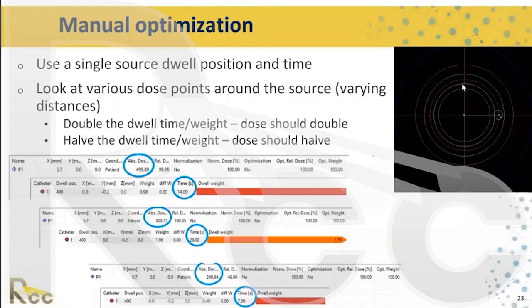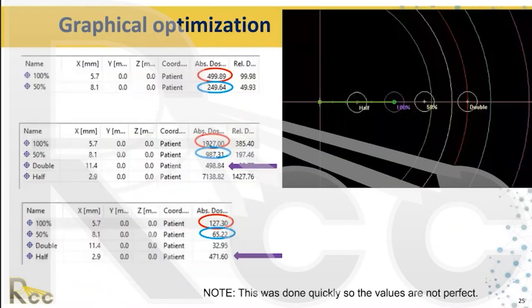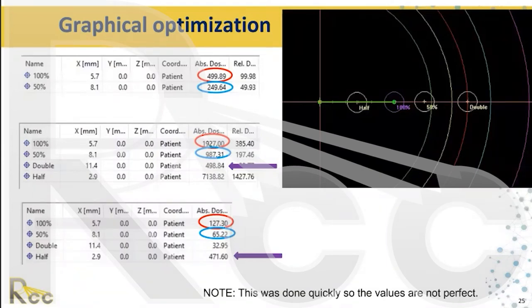After verifying dose points, increase the dwell weight and confirm dose increases at the same point; decrease the weight and confirm dose decreases. Then move the point — double the distance and observe the dose change, halve the distance and observe the dose change, confirming inverse square law behavior. For graphical optimization verification, place points at various isodose lines and verify the planning system doses against manual TG-43 calculations.